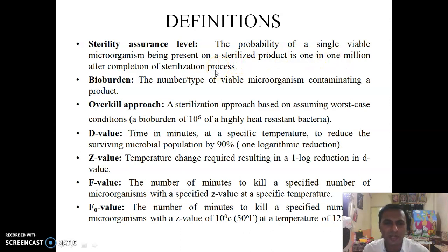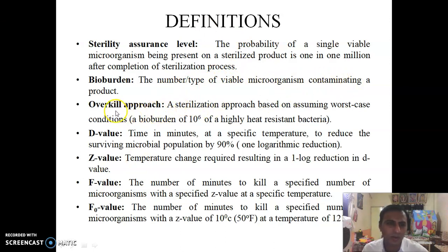Sterility Assurance Level (SAL): the probability of a single viable microorganism being present on a sterilized product is one in one million after completion of the sterilization process. Bioburden: the number or type of viable microorganisms contaminating a product. Overkill approach: a sterilization approach based on assuming worst-case conditions.